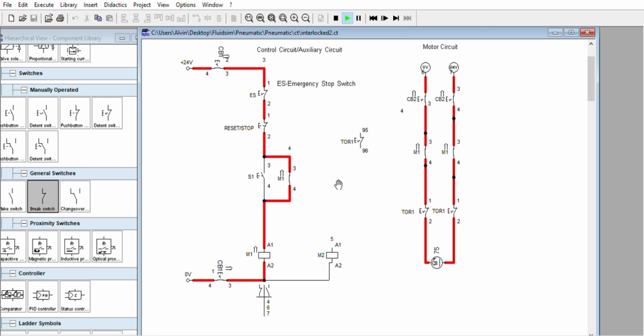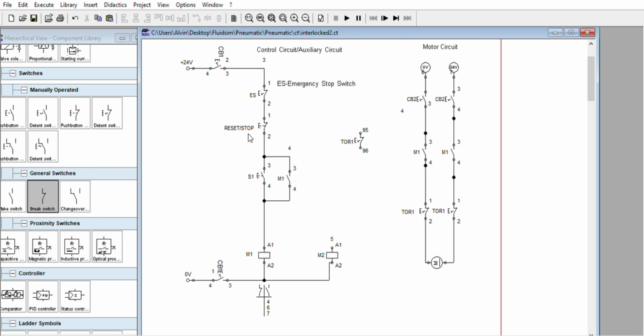And if we are going to turn on motor number 2, you will see what will happen. Copy, but we are going to change the auxiliary contact to M2. M1, holding contact of M1, holding contact of M2. You can align or whatever. The problem if you are not going to align this is it will make so many lines. You're going to align at least one line. And you can remove this one. Go directly there.